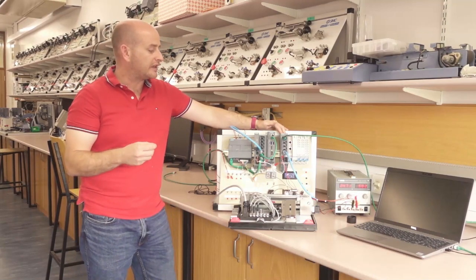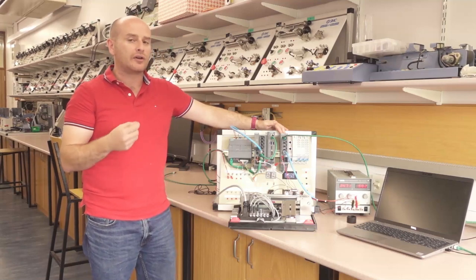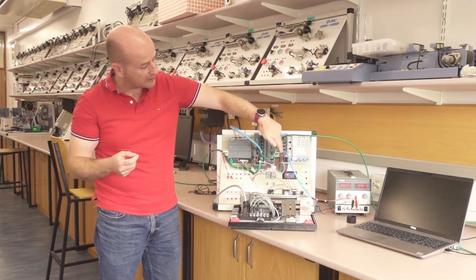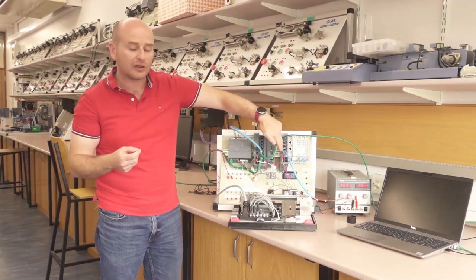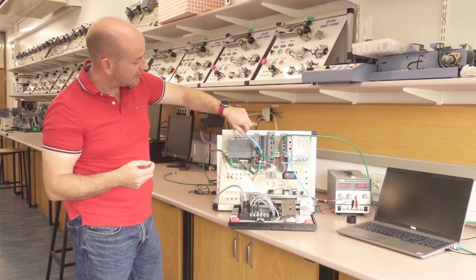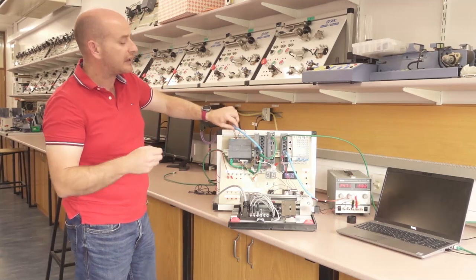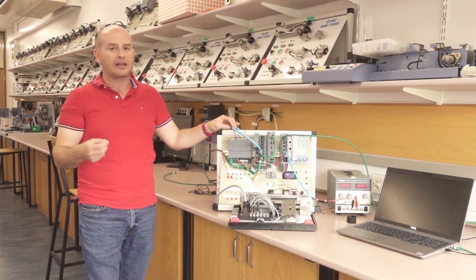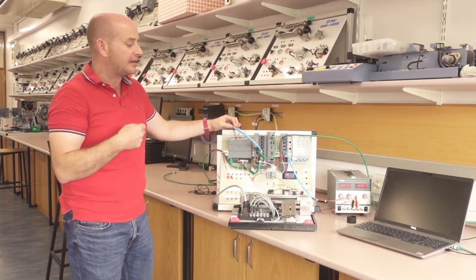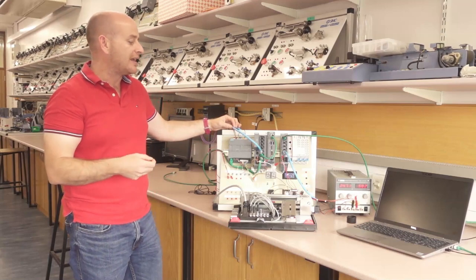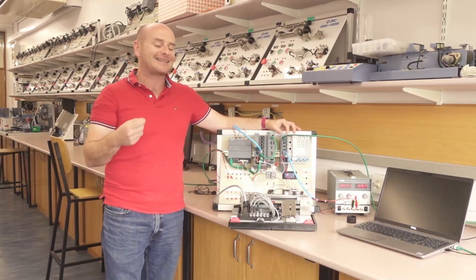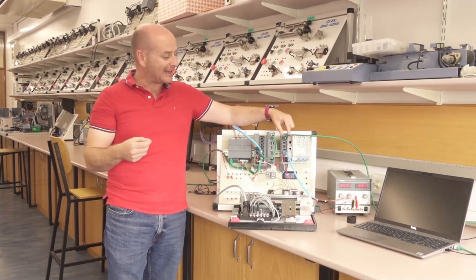The router is the gateway between our Level 2 and Level 3 networks. The router itself is being configured into two virtual LANs. We have VLAN 1, which consists of these four ports here—this is our production Level 2 network. This is connected back into our automated switch where it's plugged directly into all the Level 2 networking infrastructure and can gather data from that Level 2 infrastructure.